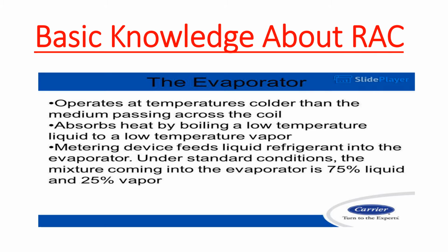Metering device feeds liquid refrigerant into the evaporator. Under standard conditions, the mixture coming into the evaporator is 75% liquid and 25% vapor.